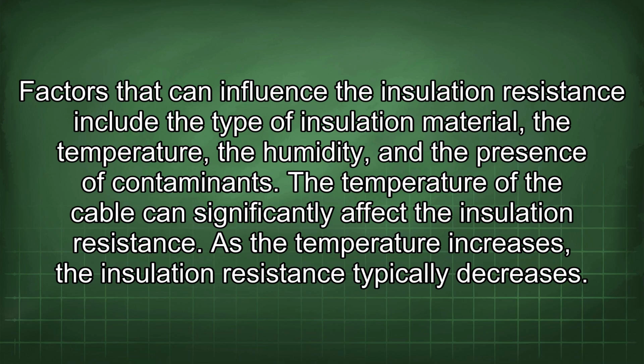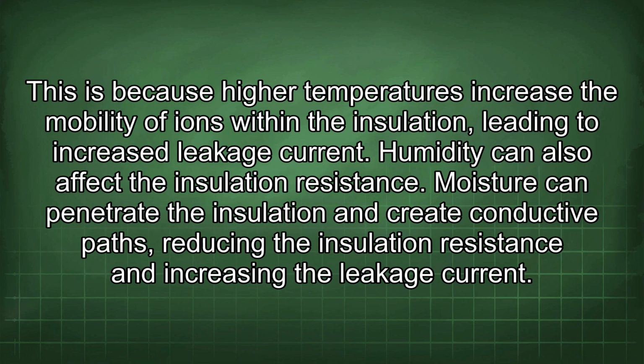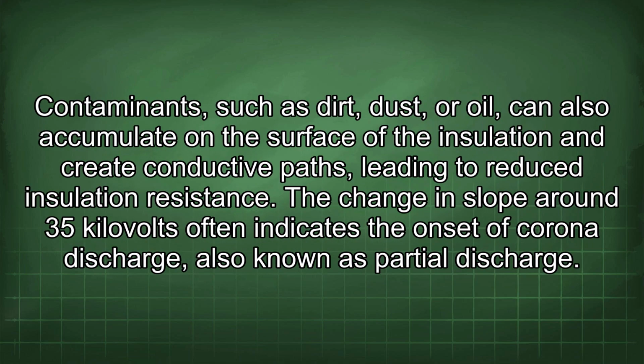Factors that can influence the insulation resistance include the type of insulation material, the temperature, the humidity, and the presence of contaminants. The temperature of the cable can significantly affect the insulation resistance. As the temperature increases, the insulation resistance typically decreases. This is because high temperatures increase the mobility of ions within the insulation, leading to increased leakage current. Humidity can also affect the insulation resistance. Moisture can penetrate the insulation and create conductive paths, reducing the insulation resistance and increasing the leakage current. Contaminants such as dirt, dust, or oil can also accumulate on the surface of the insulation and create conductive paths, leading to reduced insulation resistance.